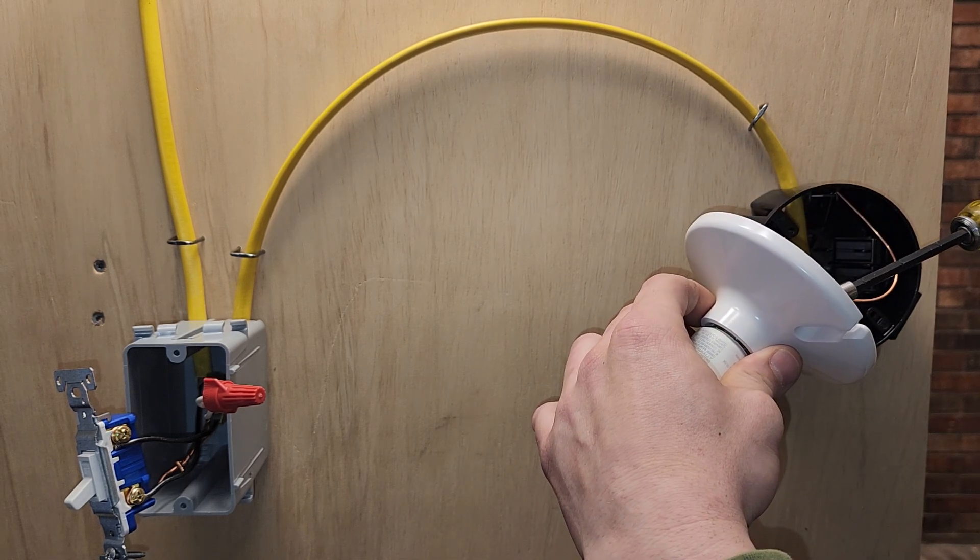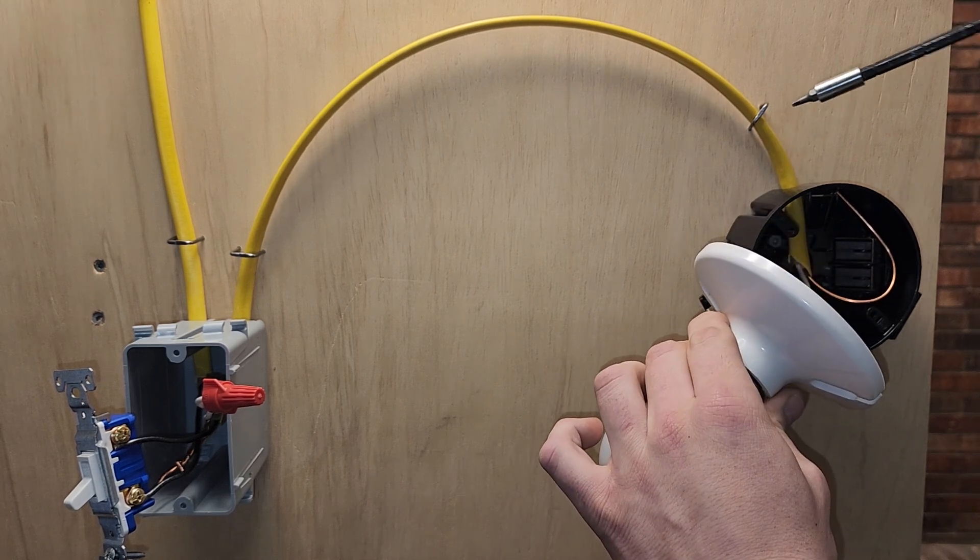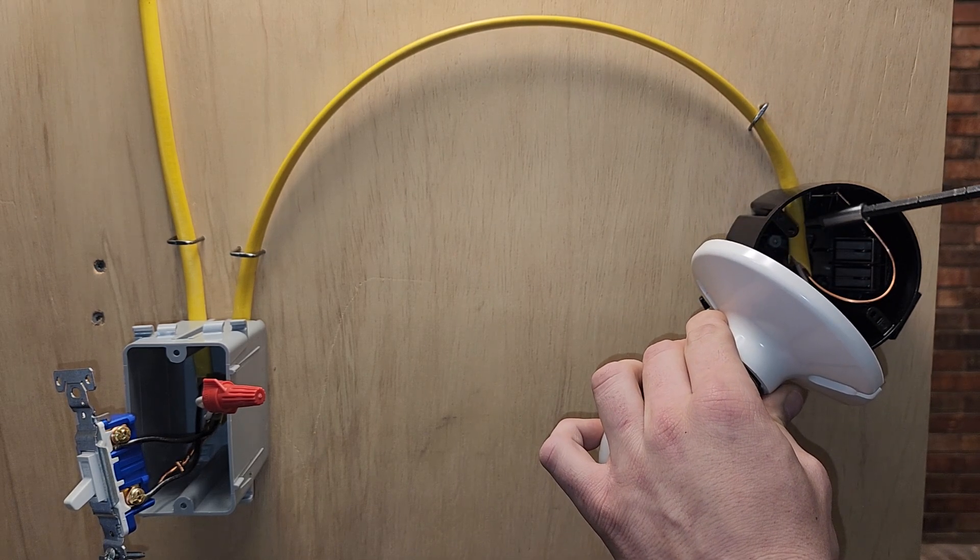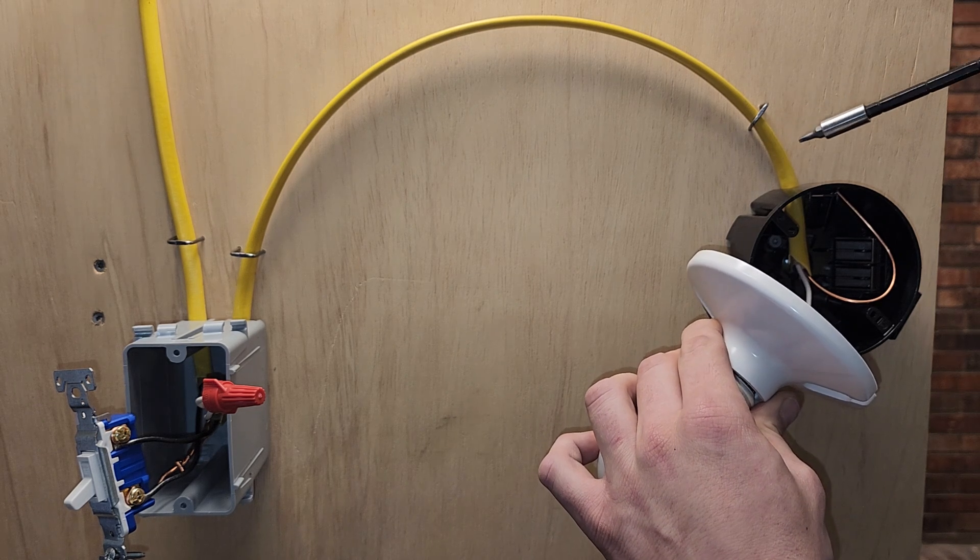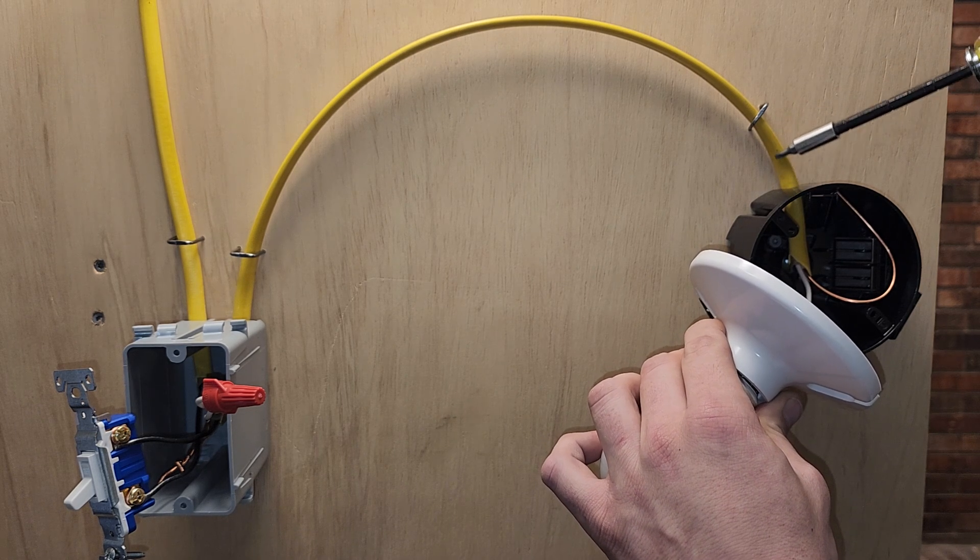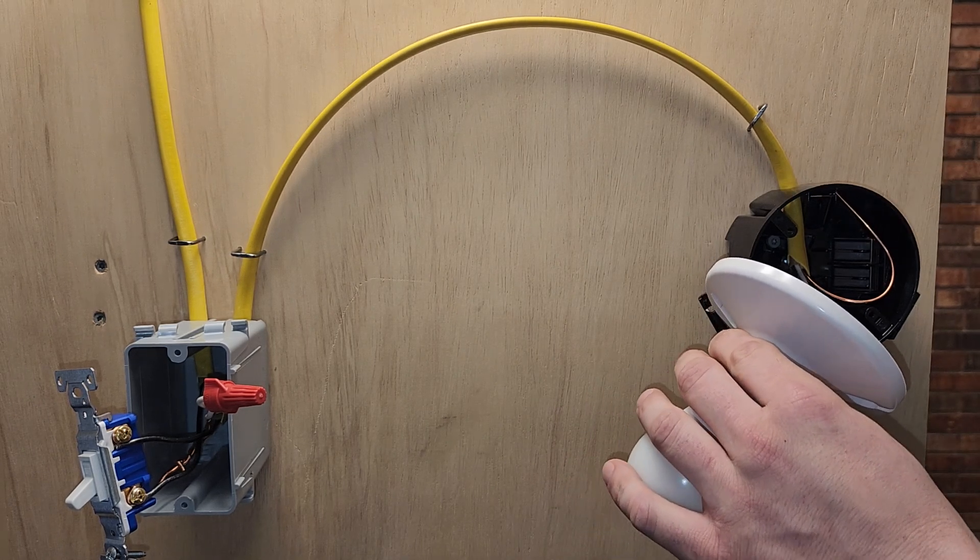Another thing to pay attention to, you can't strip this jacket out. This jacket has to be within a quarter inch inside this box. You can't strip this wire out here and have the black, white, and ground exposed outside this box. It has to be inside of the box at least a quarter of an inch.